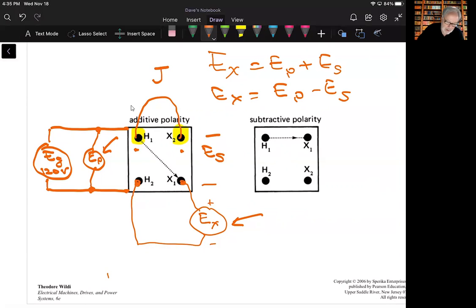Another thing I'll point out: in making this test, we use an ordinary 120 volt, 60 hertz source connected to the high voltage side, so you could actually do this test safely. That's something a technician or engineering technologist might do with a particular transformer disconnected from very high voltages. Now let's continue and look at an actual example with some numbers.